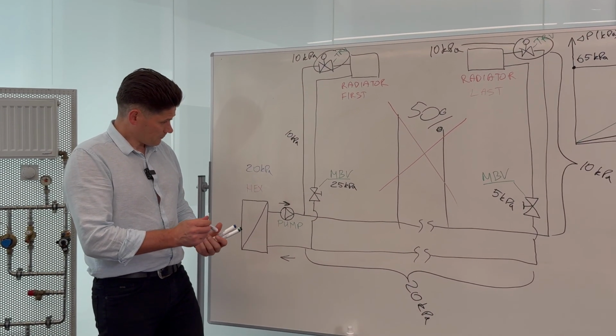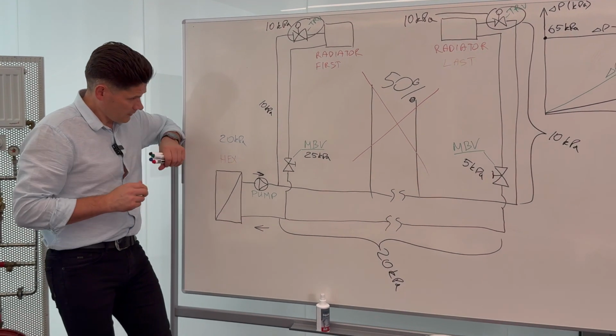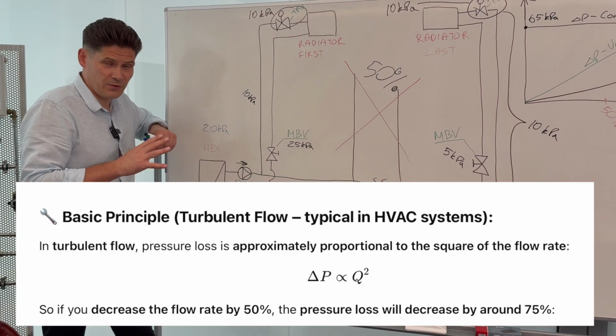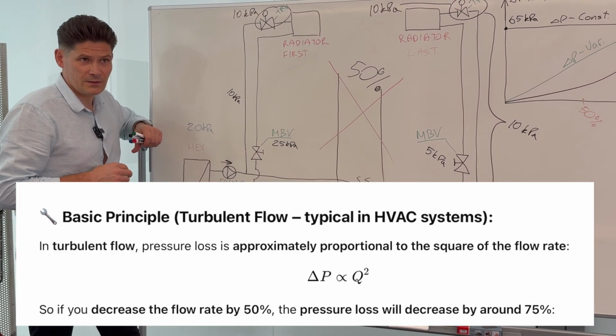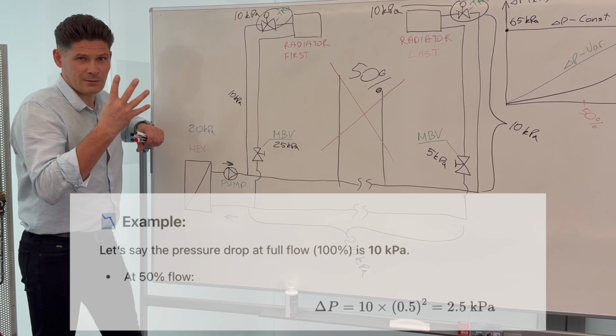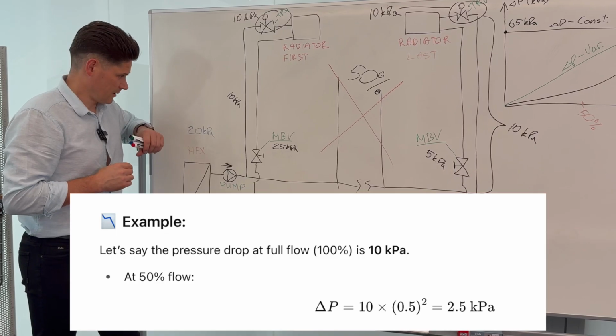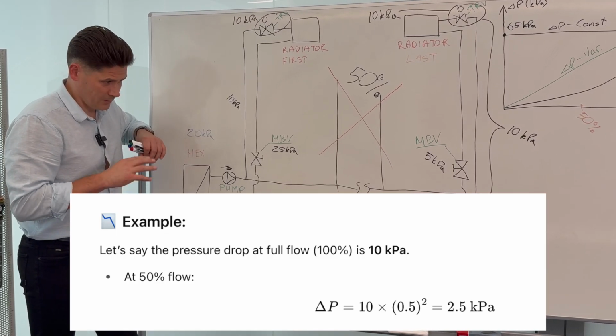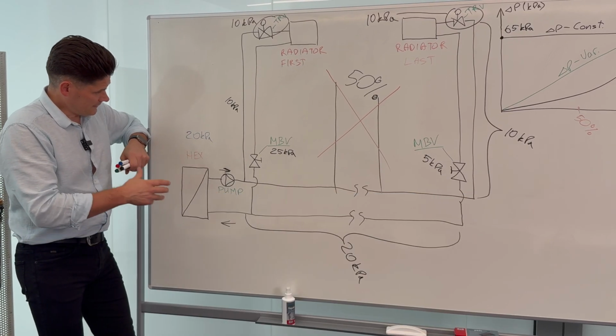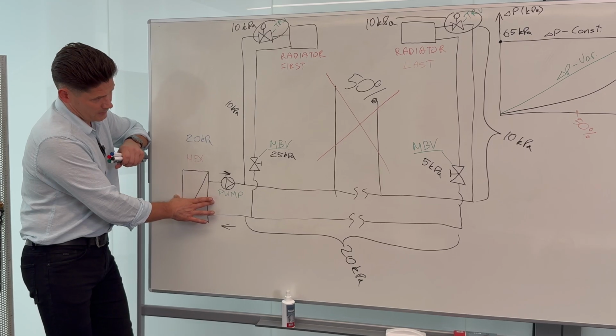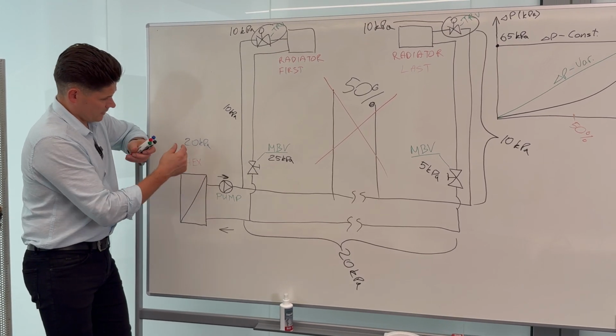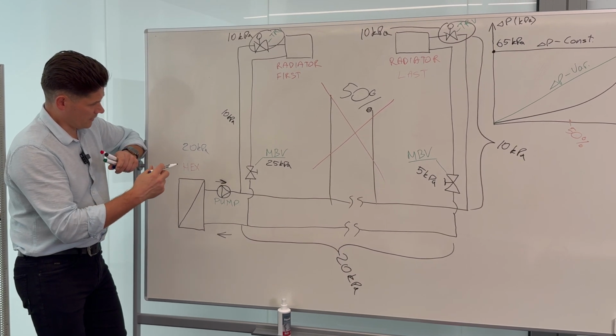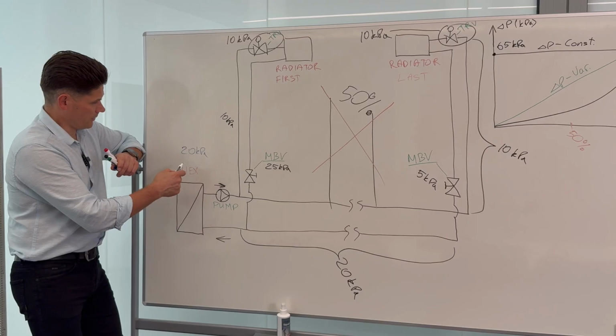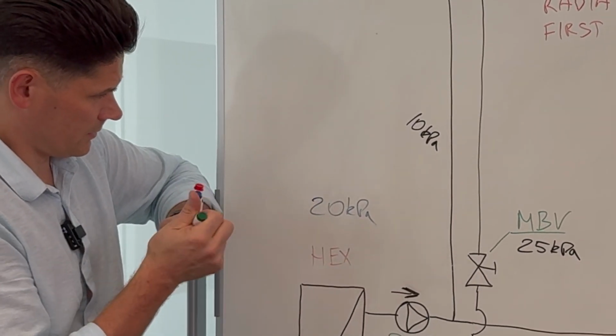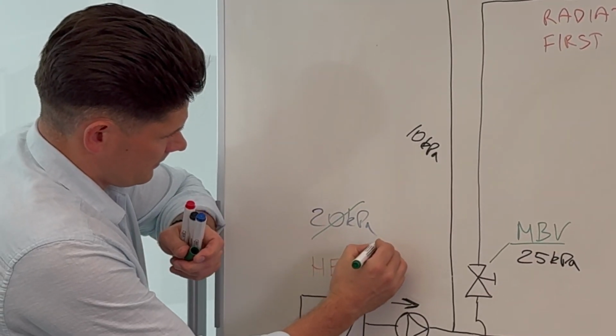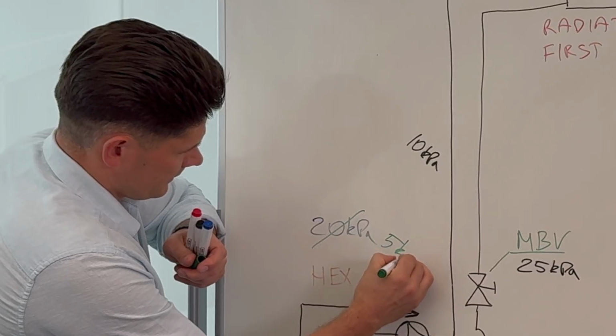According to the formula, if my flow is going down to half, to 50%, then pressure losses in a system usually go down 4 times. It's nearly 4 times. I'm not going into very much detail, but you can check. Let's say this heat exchanger is now working at 50% flow. So this pressure loss now goes down, I need to divide by 4. So the new setup, the new delta P here, will be not 20, but dividing by 4, it will be 5 kilopascals.